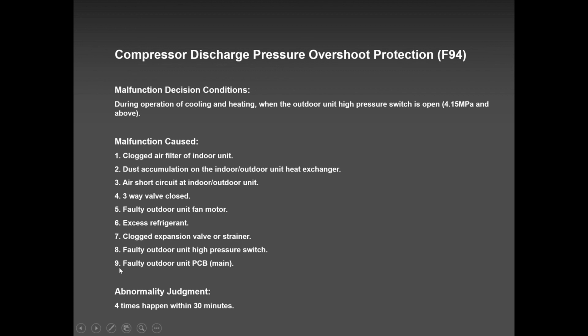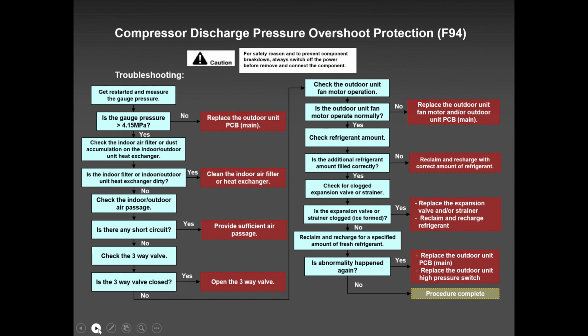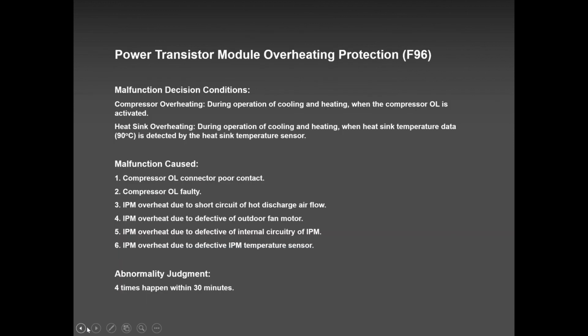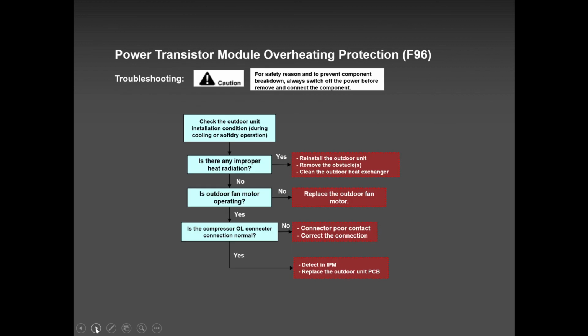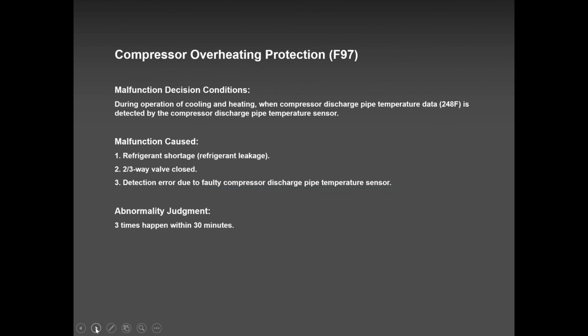F94, very rare, but it can happen. And if it happens, this is the issue. There are so many error codes under F and under H, but I'll tell you one thing, most of these error codes are dead on. F96, if you get it, definitely the outdoor PCB. F97, never had this before, but again, if you get it, check all these issues.